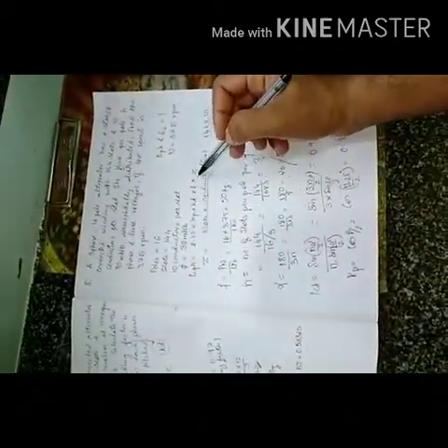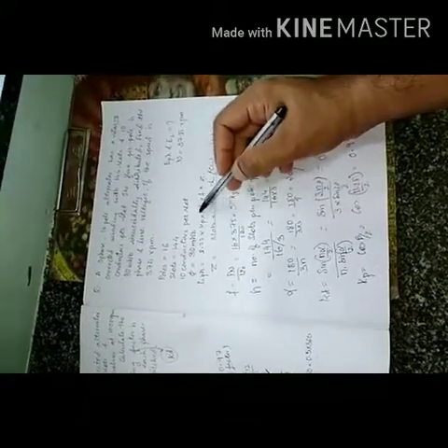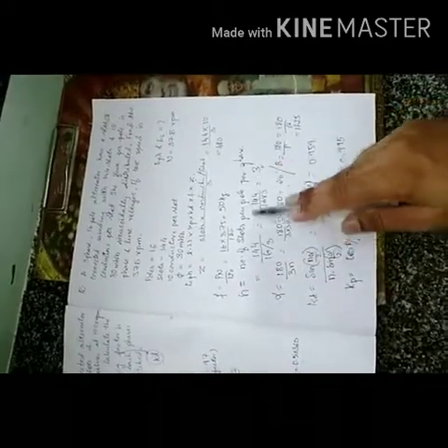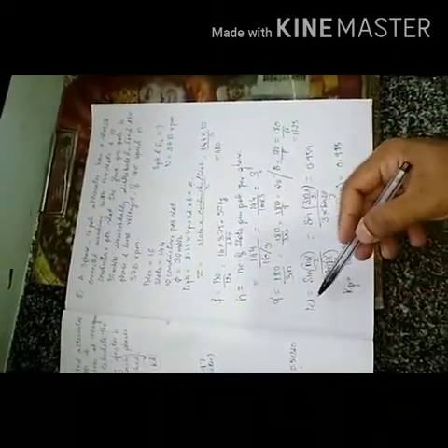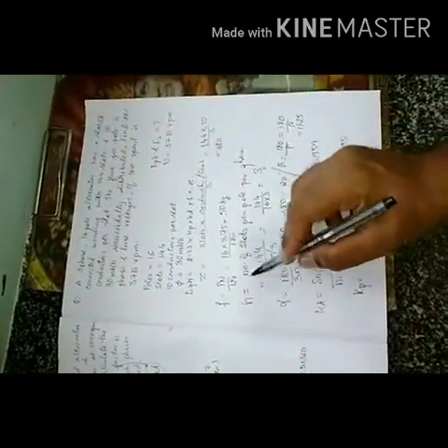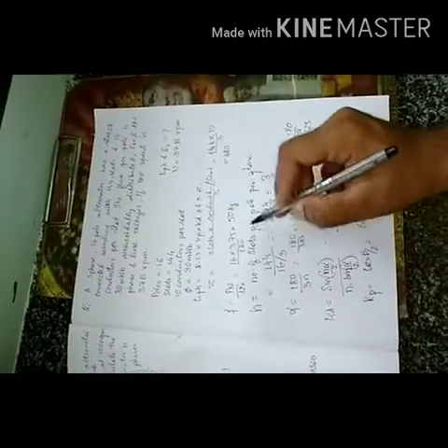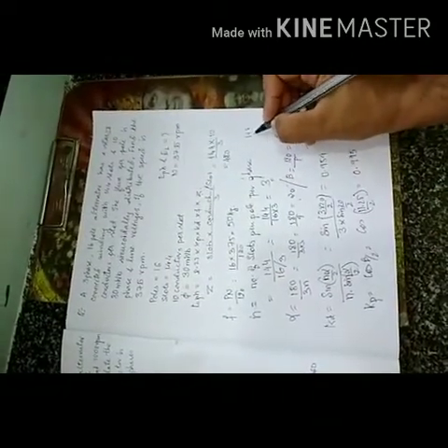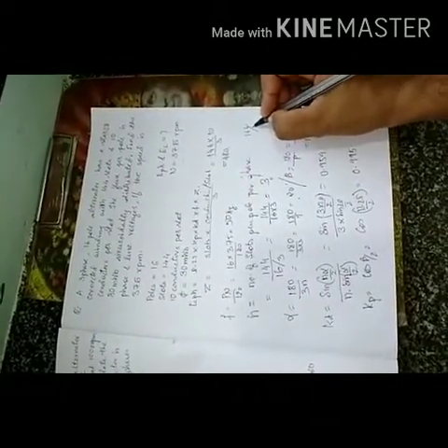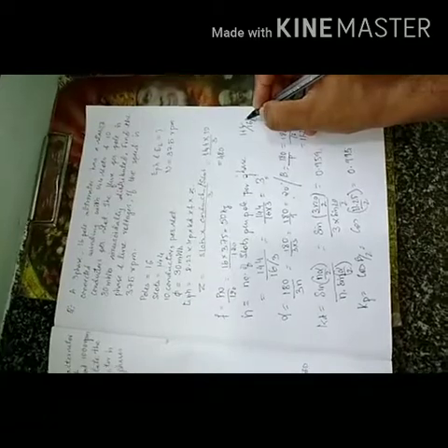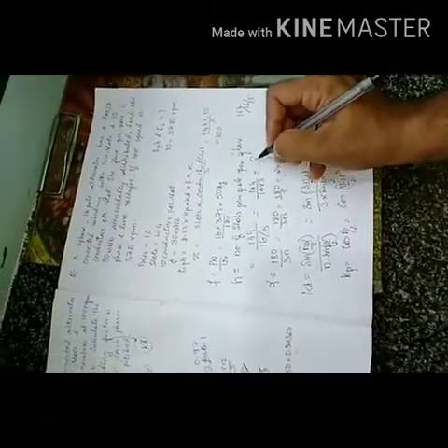So this is how you have to calculate the value of Z, f, Kp and Kd. If you know how to calculate the value of n, alpha and beta, it is easy to calculate Kd and Kp. I just need to substitute the values of n, alpha and beta. The only consideration is how you calculate n. It is the number of slots per pole per phase. Number of slots are 144, per pole, again per phase, so it is all divided. You just take 3 to the lower side, so it is 144 by 16 into 3, which gives me 3.